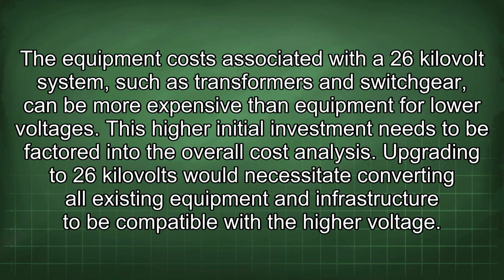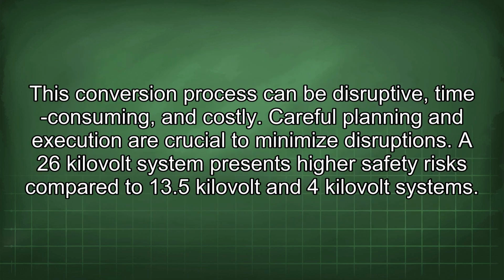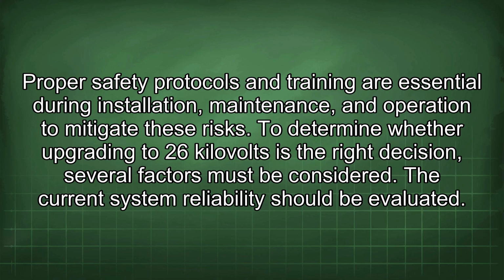The equipment costs associated with a 26 kilovolt system, such as transformers and switchgear, can be more expensive than equipment for lower voltages. This higher initial investment needs to be factored into the overall cost analysis. Upgrading to 26 kilovolts would necessitate converting all existing equipment and infrastructure to be compatible with the higher voltage. This conversion process can be disruptive, time-consuming, and costly. Careful planning and execution are crucial to minimize disruptions. A 26 kilovolt system presents higher safety risks compared to 13.5 kilovolt and 4 kilovolt systems. Proper safety protocols and training are essential during installation, maintenance, and operation to mitigate these risks.